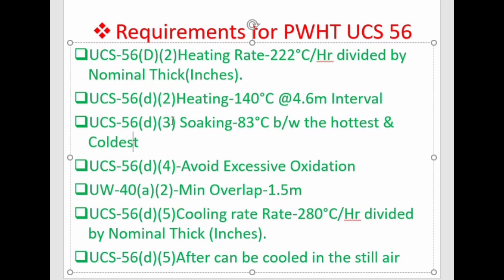The third statement is UCS-56 D3: during the holding time, there shall not be a greater difference than 83°C between the highest and lowest temperatures throughout the portion of the vessel being heat treated. During soaking — the period of constant temperature — there shall not be a temperature gradient greater than 83°C in any part of the vessel.